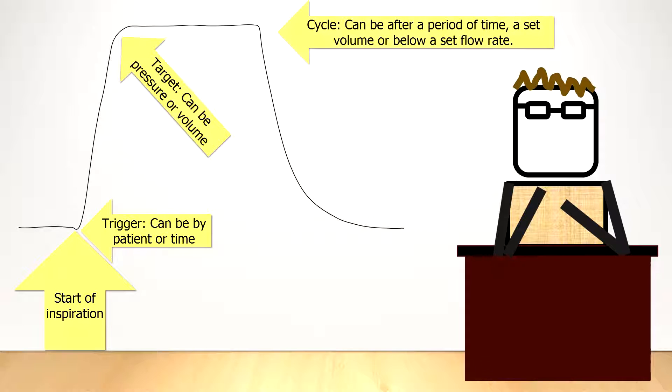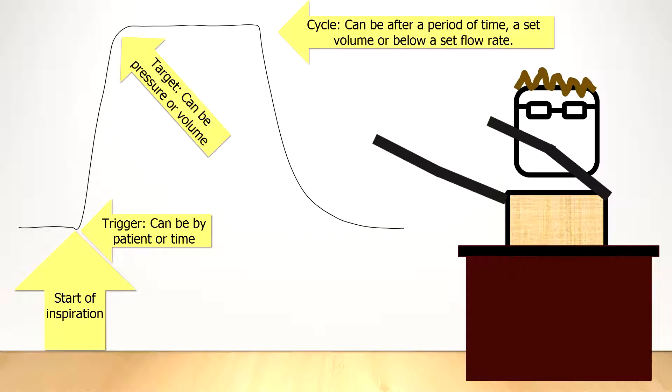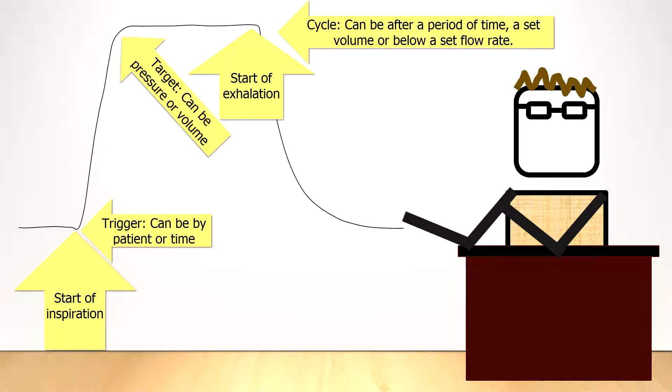The final phase of the ventilator cycle is cycling. Cycling marks the end of inspiration and the start of exhalation. It can occur after a set period of time, such as the inspiratory time, or after a set volume has been delivered, or after a point where the set flow rate drops below a certain level.